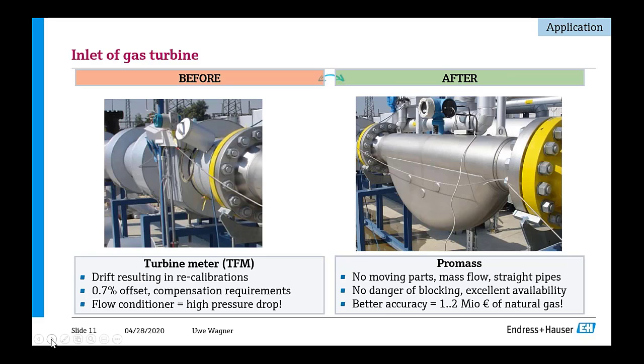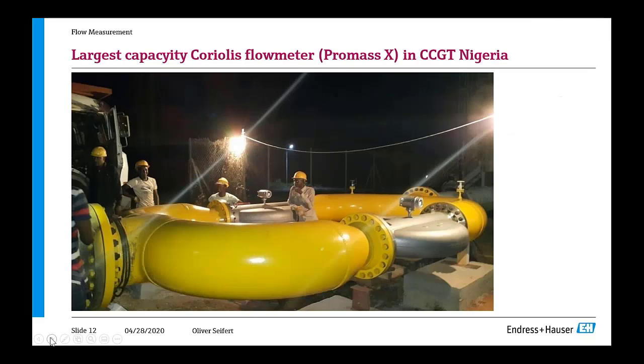Here's an example where we replaced a traditional meter, a turbine flow meter, the TFM. When this customer installed the ProMass, he found a drift between the turbine and the ProMass. At first he thought our mass flow meter was wrong, but he found out later, because both meters were sent for calibration on natural gas at PTB, a custody transfer authority in Europe, that the turbine had an offset of 0.7%. This customer told us that this accuracy improvement meant savings of 1 to 2 million euros of natural gas per annum. So a very interesting reference here from Europe in the Munich area.